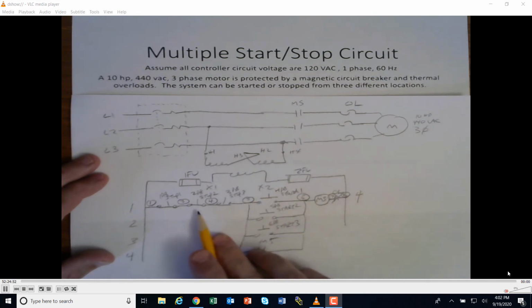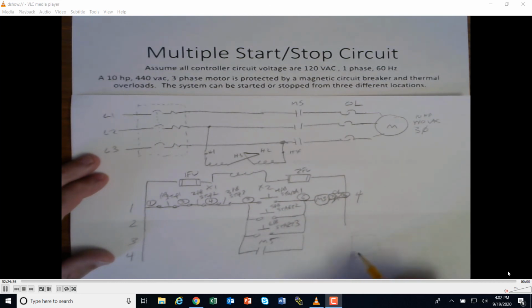By the way, you'd look for this somewhere - there's going to be a panel with a start button and a stop button, and the wires need to run in the order so that they work. Somewhere else there's going to be another start and stop, so somehow there are wires running between these in a series and parallel combination. It's a little tricky wiring, but you could do it based on the wire numbers here and the ladder logic.